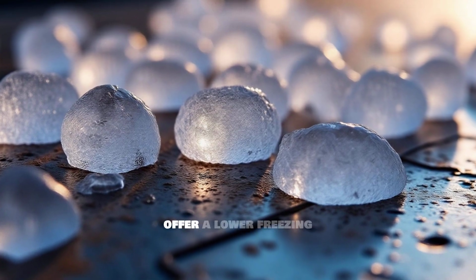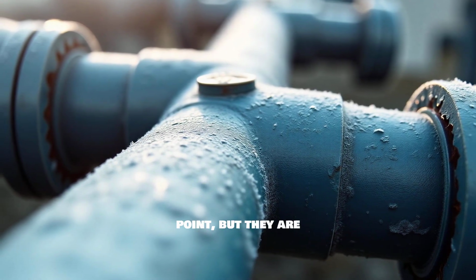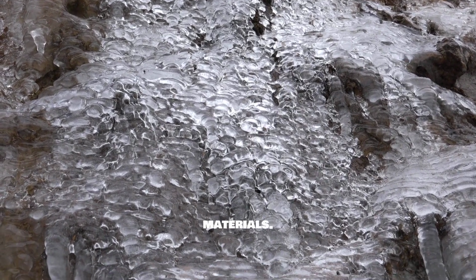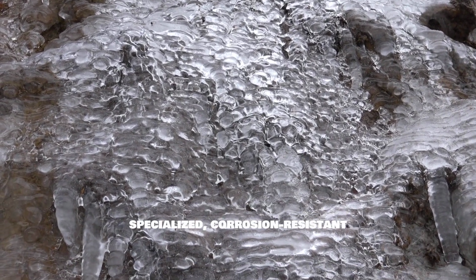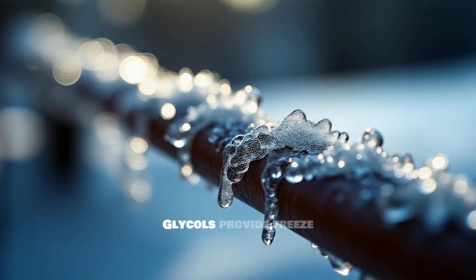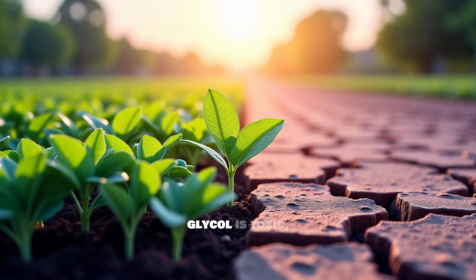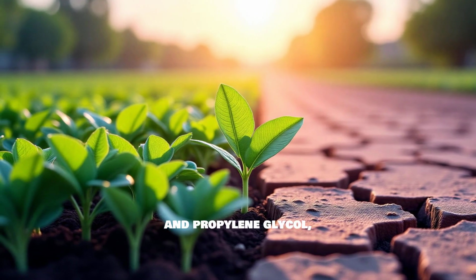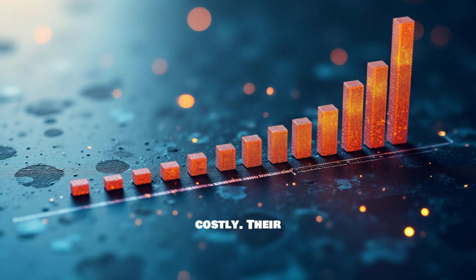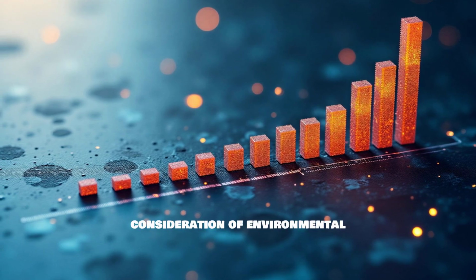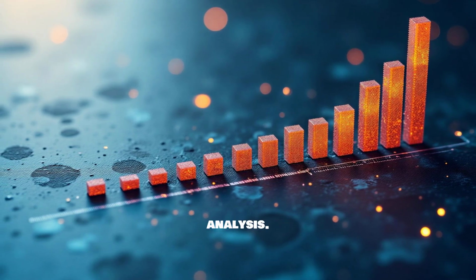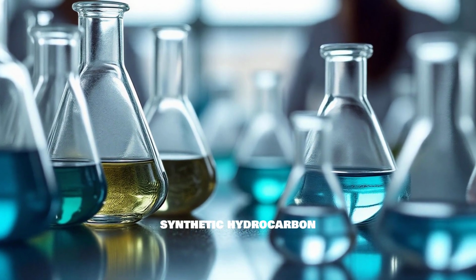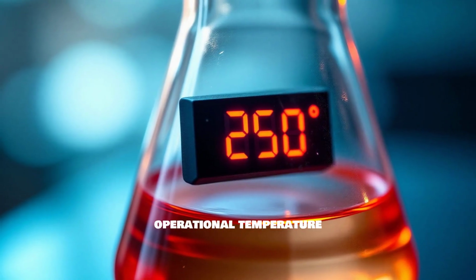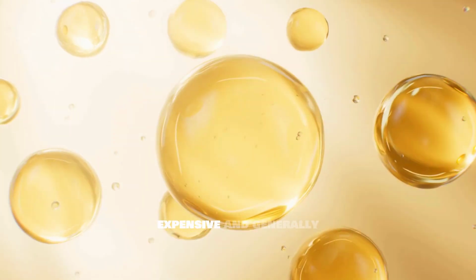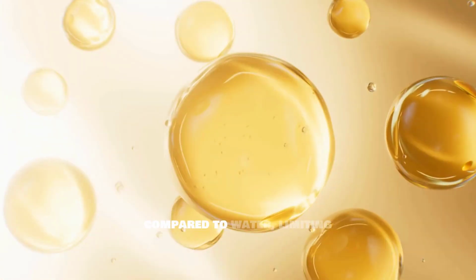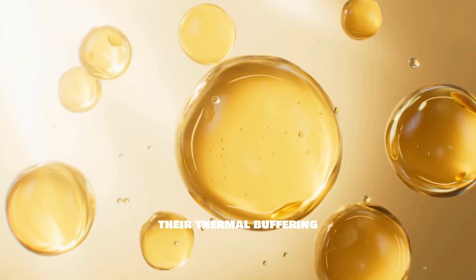Salt or brine solutions offer a lower freezing point, but they are corrosive to many common construction materials. This necessitates specialized, corrosion-resistant containment and piping. Glycols provide freeze protection, but ethylene glycol is toxic, and propylene glycol, while safer, is more costly. Their use requires careful consideration of environmental impact and cost-benefit analysis. Silicone oils or synthetic hydrocarbon fluids offer a wide operational temperature range. However, they are expensive and generally possess lower heat capacities compared to water, limiting their thermal buffering capability.